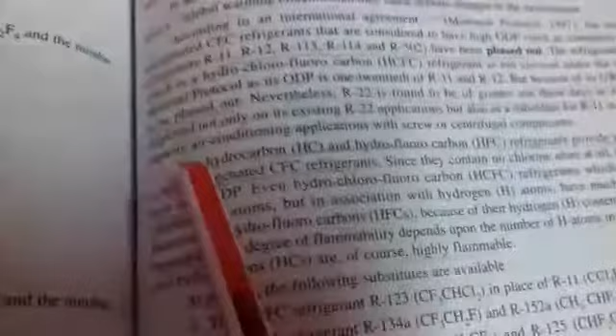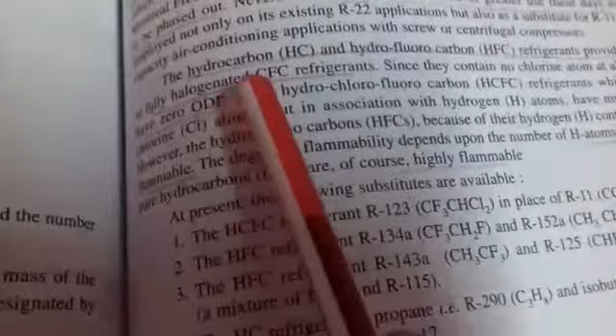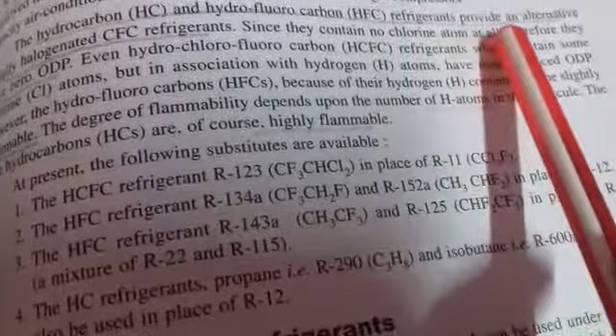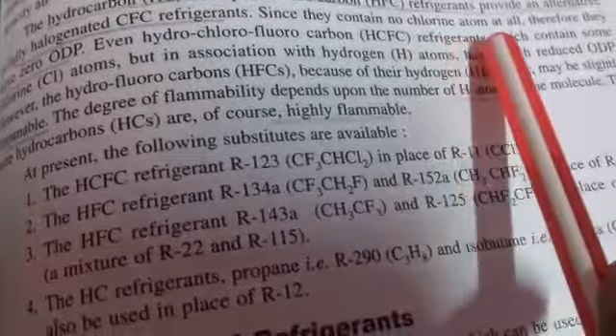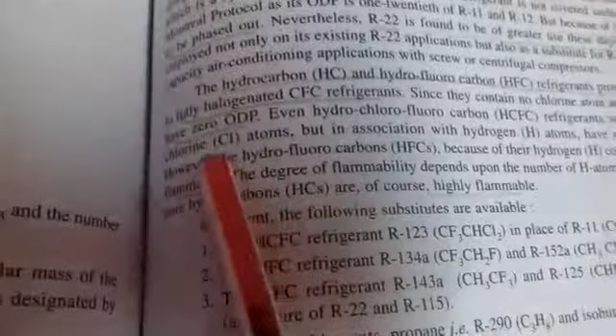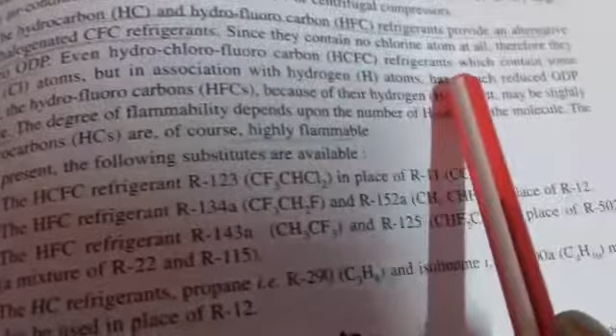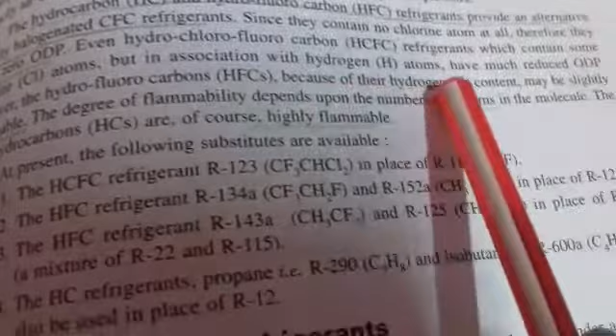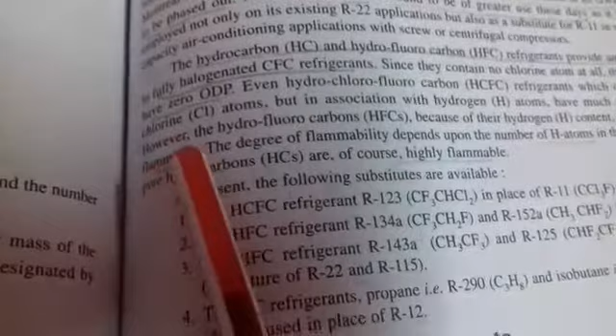The hydrocarbon and hydrofluorocarbon HFC refrigerants provide an alternative to the fully halogenated CFC refrigerants, since they contain no chlorine atom at all. Therefore they have zero ODP. Even hydrochlorofluorocarbon refrigerants, which contain some chlorine atoms but in association with hydrogen atoms, have much reduced ODP. However, the hydrofluorocarbons are flammable because of their hydrogen; the degree of flammability depends upon the number of hydrogen atoms in the molecule. The pure hydrocarbons are of course highly flammable.